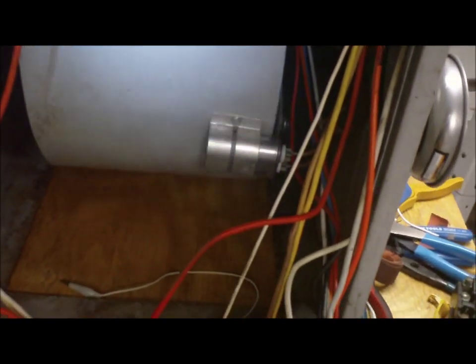Let's see here, I don't know if you guys can see it or read it at all, but I try to get it as best as I can. But this one's for your MV, which is for your main valve. There's two of them. I can see if I can look at it in here. That's where your ignition control unit hooks up to, for your pilot valve, main valves and stuff, and your on and off switch for your gas. And right underneath, your blower motor and your run capacitor.